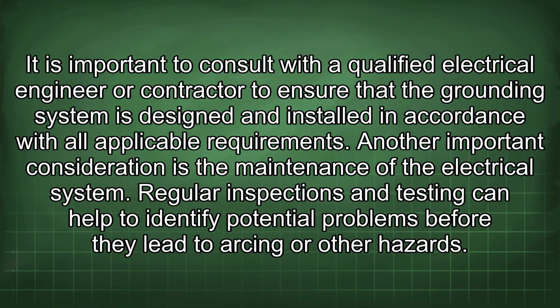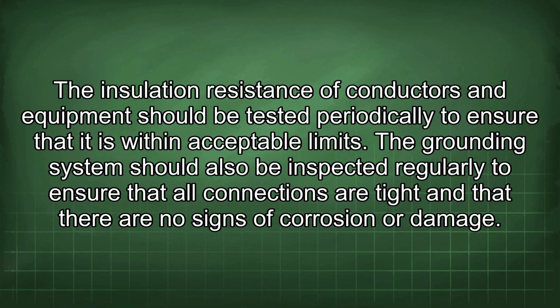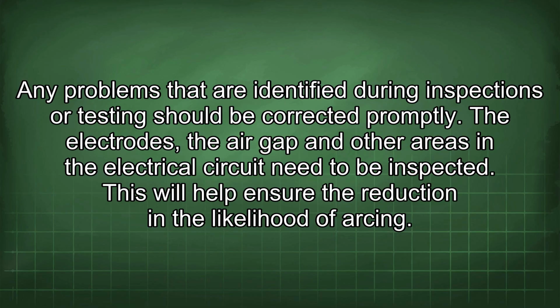Another important consideration is the maintenance of the electrical system. Regular inspections and testing can help to identify potential problems before they lead to arcing or other hazards. The insulation resistance of conductors and equipment should be tested periodically to ensure that it is within acceptable limits. The grounding system should also be inspected regularly to ensure that all connections are tight and that there are no signs of corrosion or damage. Any problems that are identified during inspections or testing should be corrected promptly. The electrodes, the air gap, and other areas in the electrical circuit need to be inspected. This will help ensure the reduction in the likelihood of arcing.